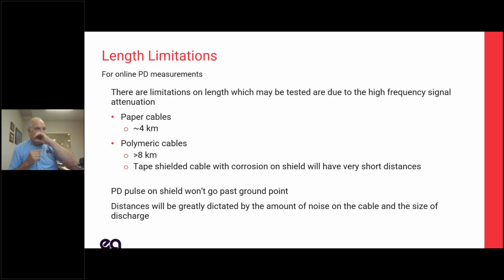But if you're testing a 5-kilometer cable, you might not be able to detect as low a PD level as you could on a 4-kilometer cable, that sort of thing. Tape shielded cables, where they're in a wet environment and they have lots of corrosion, are going to get high inductive and you're not going to be able to test them much at all. But if you've got good clean shields, you should be able to go a few kilometers reliably.